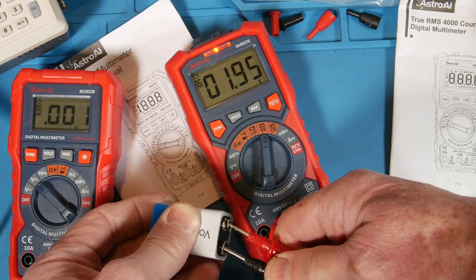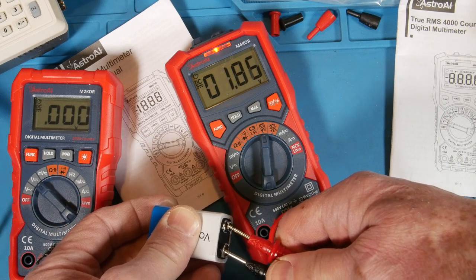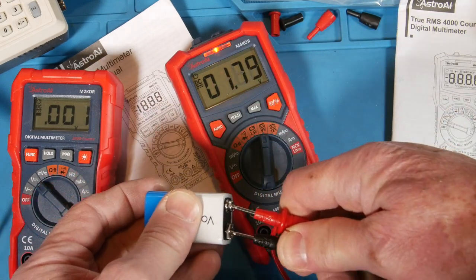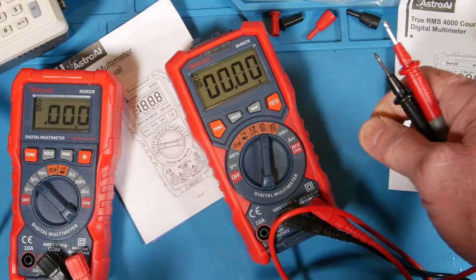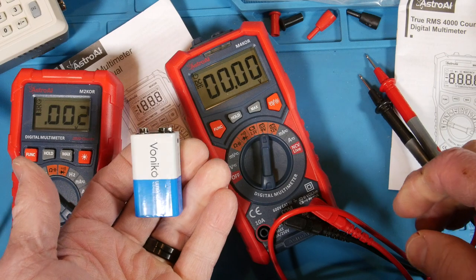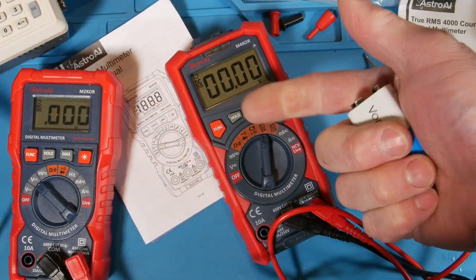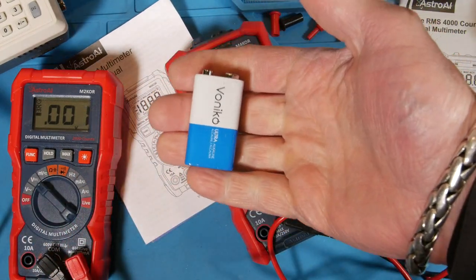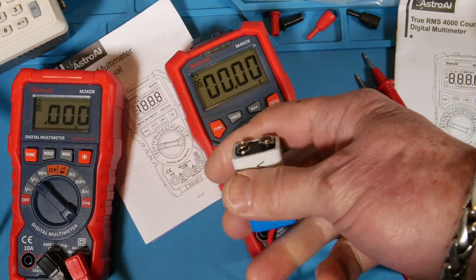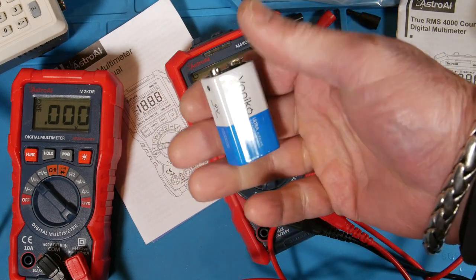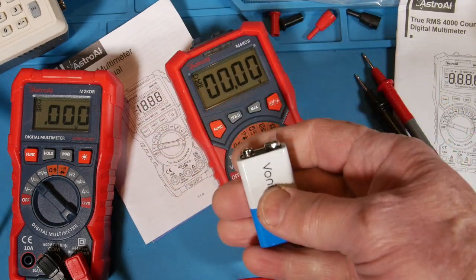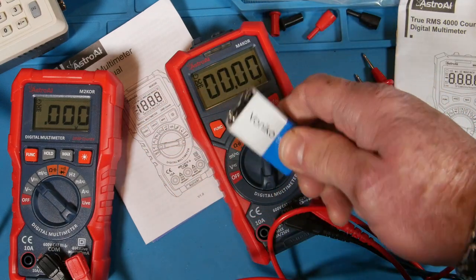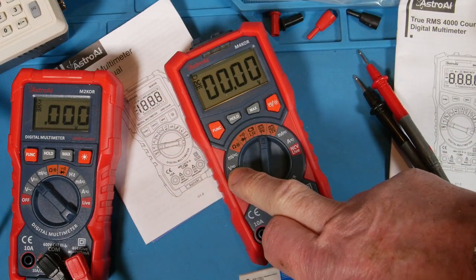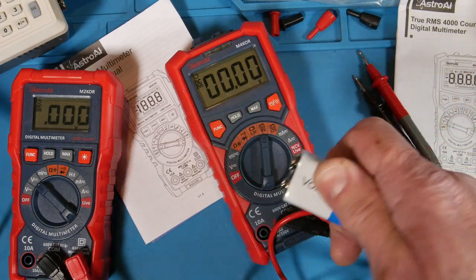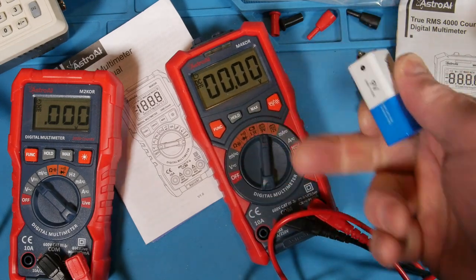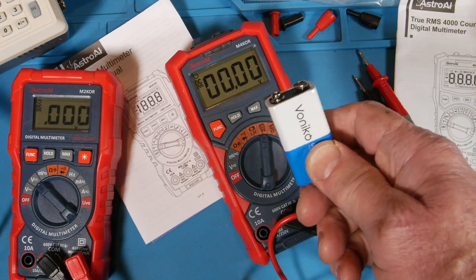2 volts, and it's even dropping with the load. See the red light? It's saying nope, that's no good. If this was almost good and it was reading like 8.8 and it dropped down to 7 volts once you put a load, then you'd know it was a bad battery. But in this case, it was bad whether you measured it here or here. That's the value, you see how it puts a load and drops the voltage.